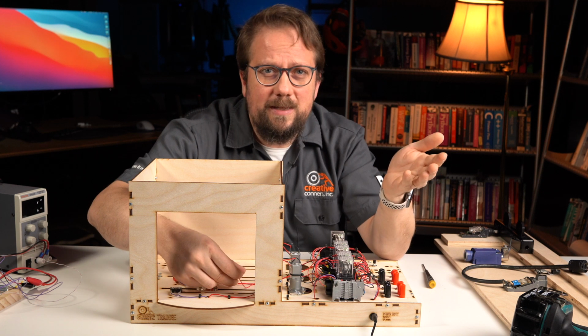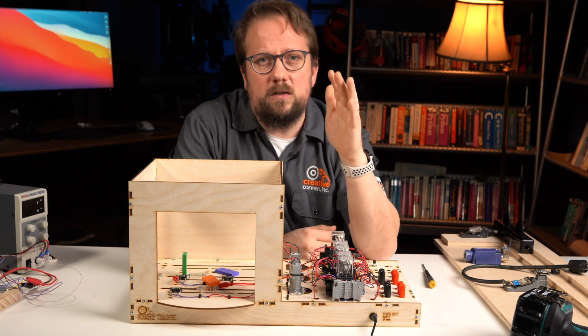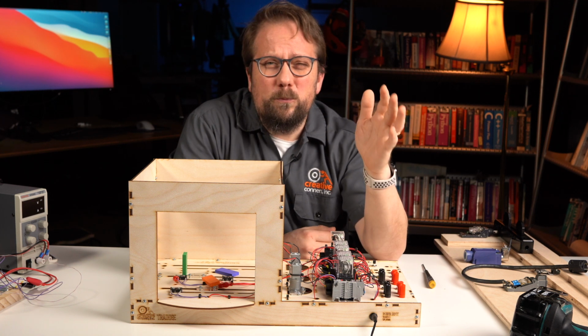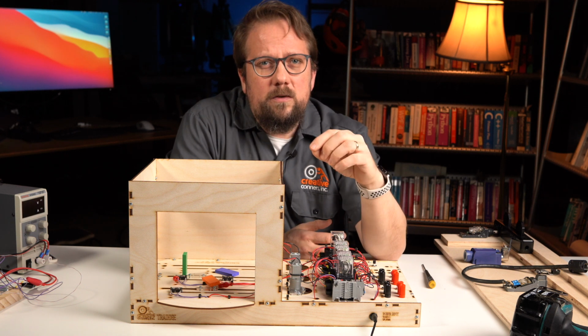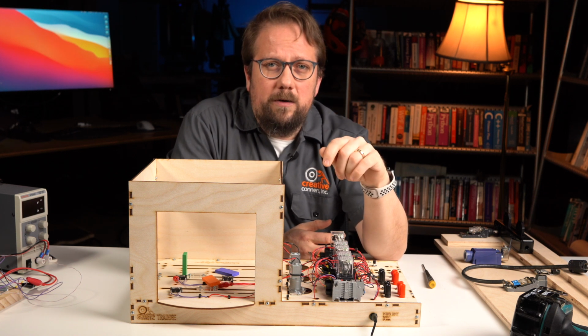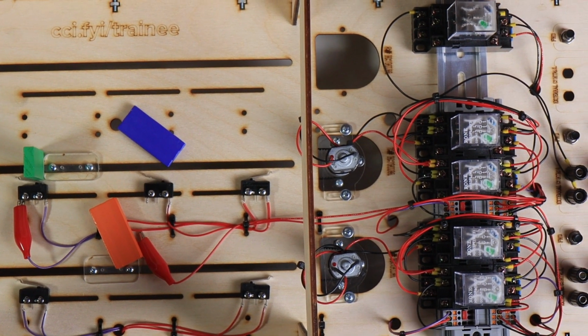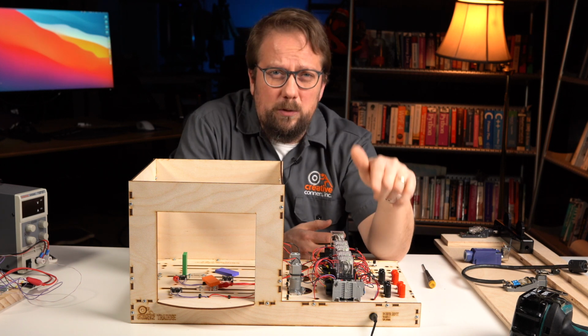And the controls have no idea that the wire was cut, because the whole design assumes that everything is just fine until it hears from the limit switch. That's really optimistic. This method works okay as long as there isn't a failure in the wiring, but it falls apart as soon as anything goes wrong. We can't have that in a device that is meant to stop a motor.